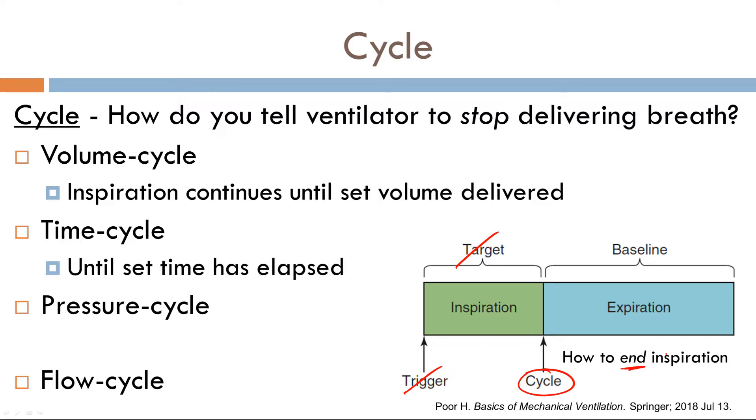What about time cycle? In time cycle, the vent will continue to deliver breath until a certain time has elapsed. So for example, if I've set it to 1.2 seconds, once 1.2 seconds has elapsed, boom, stops delivering your breath.